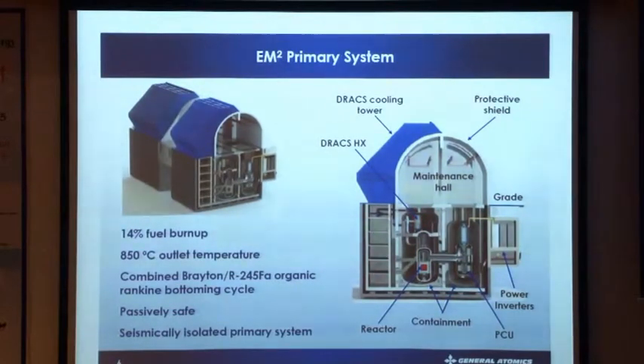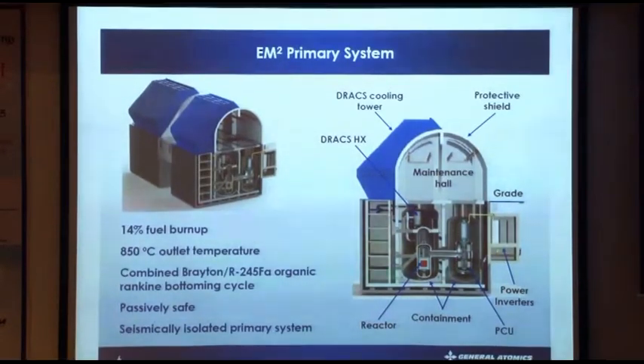These systems over here are the DRACs, the direct reactor auxiliary cooling system heat exchanger and circulators, which is a helium to helium heat exchanger. And from there, the decay heat is rejected to the air by these cooling towers, which are the DRAC's cooling towers. Another thing, in order to maintain a very standardized design, this was one of the great inputs we received from the shop: everything above this, which is the main reactor building, should be on a seismically isolated platform, so that it can be installed in many locations only by the design of the seismic isolators, which they did in the EM2.